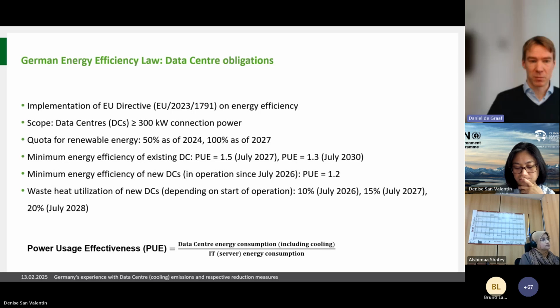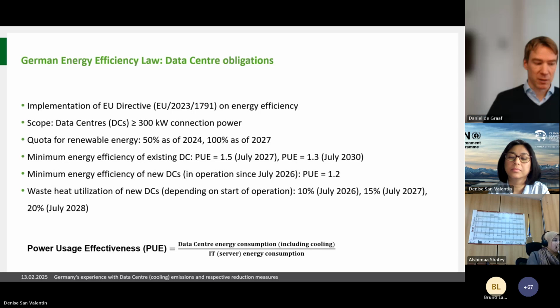There have to be minimum energy standards fulfilled in existing data centers, which is a PUE, power usage effectiveness, of 1.5 from July 2027, and a PUE of 1.3 from July 2030 on. PUE, as Anderson Alves and Bruno Lafitte explained, is the data center energy consumption, which includes the cooling energy consumption, divided by the IT energy consumption. This ratio is the PUE.